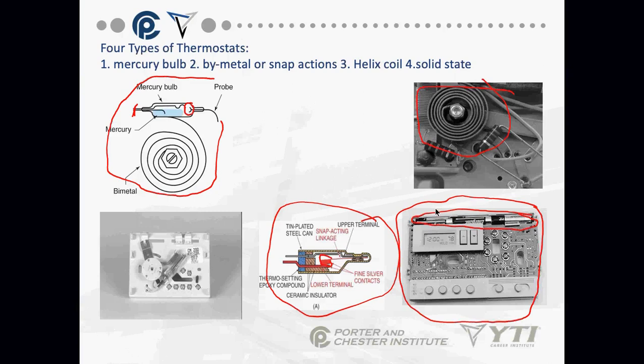Now, there is an interesting thing, and when we get to our schematics of this, I'm going to show it to you. If you have a thermostat with batteries, and it's an older style thermostat, if your batteries go dead, the thermostat will not operate in cooling mode. It will still operate in heating mode, but in cooling mode, if the batteries go dead in some of these thermostats, it will not operate.